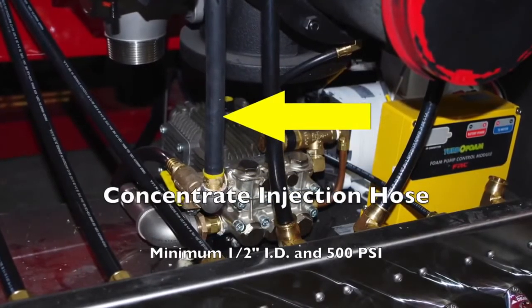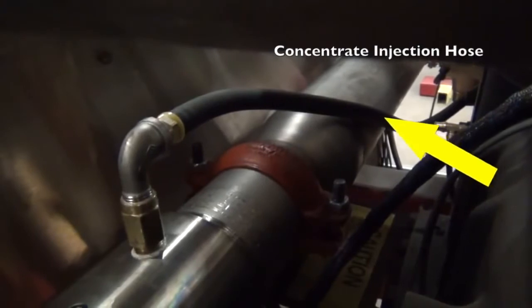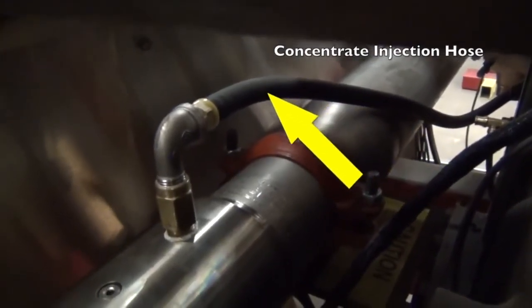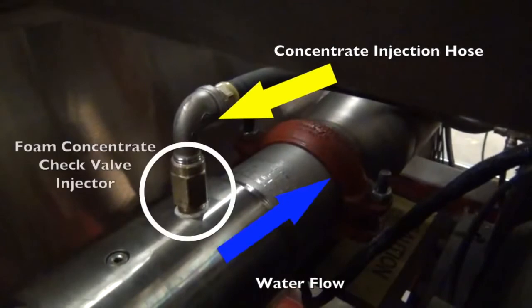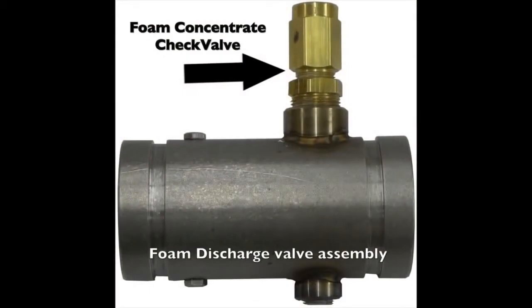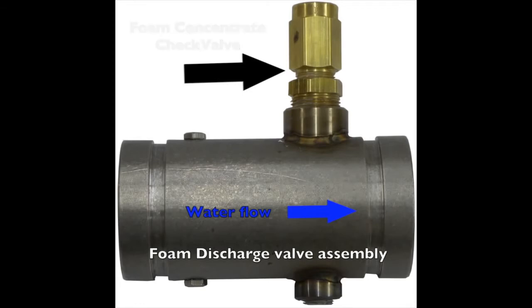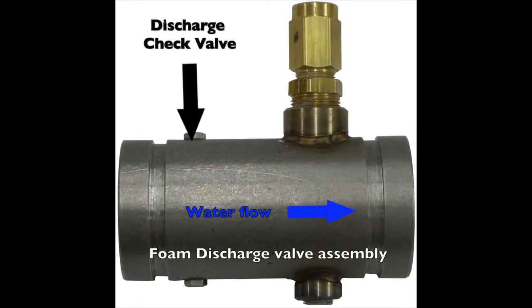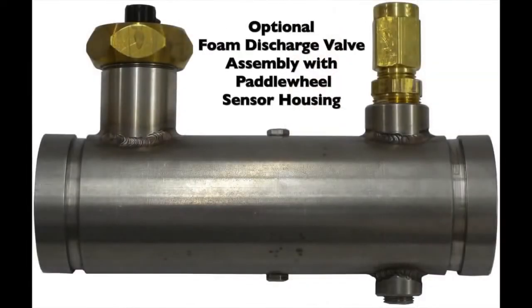The foam concentrate injection hose must have at least a 1/2 inch inside diameter and be rated for at least 500 psi. The foam concentrate injection hose connects to the foam concentrate check valve injector. This is a Fire Research foam discharge valve assembly with a foam concentrate check valve and discharge check valve. The foam injection point must always be downstream of the discharge check valve. Fire Research also makes a foam discharge valve assembly with a built-in paddle wheel sensor housing.